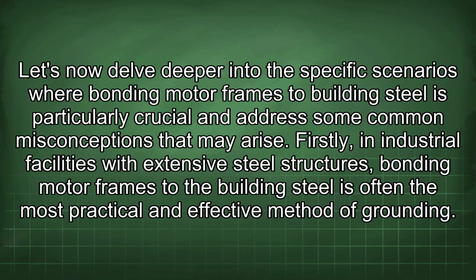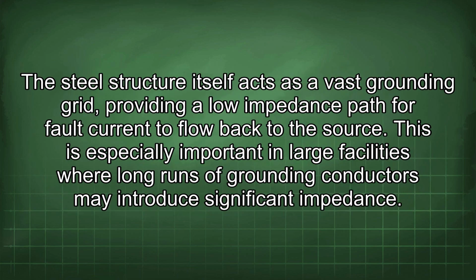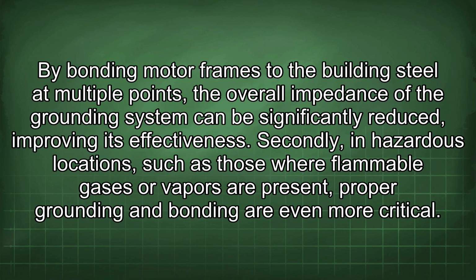Let's now delve deeper into the specific scenarios where bonding motor frames to building steel is particularly crucial and address some common misconceptions that may arise. Firstly, in industrial facilities with extensive steel structures, bonding motor frames to the building steel is often the most practical and effective method of grounding. The steel structure itself acts as a vast grounding grid, providing a low impedance path for fault current to flow back to the source. This is especially important in large facilities where long runs of grounding conductors may introduce significant impedance. By bonding motor frames to the building steel at multiple points, the overall impedance of the grounding system can be significantly reduced, improving its effectiveness.